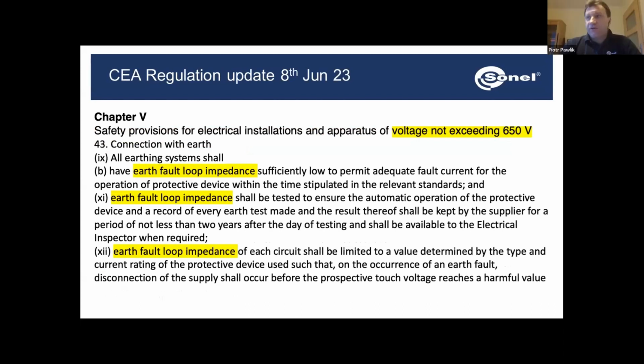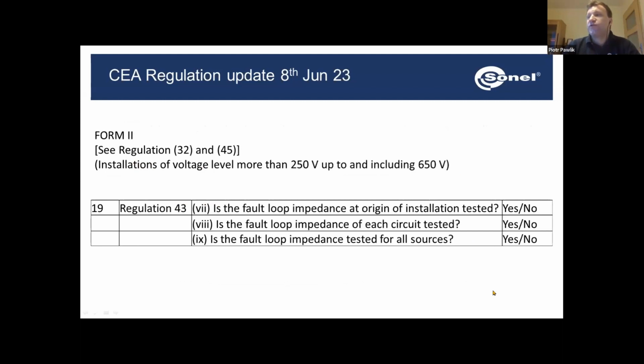All right, now as we look at the low voltage supply systems, we need to check the fault loop impedance. We need to make sure that it allows the adequate flow of the current to operate the protective device. We need to test fault loop impedance to make sure that the automatic disconnection of supply is working. And its value depends on the type of the protective device that we are using. Also, we need to make the tests at the origin of the installation. So on the transformers, we need to check the fault loop for each circuit. And we need to do this for all sources.